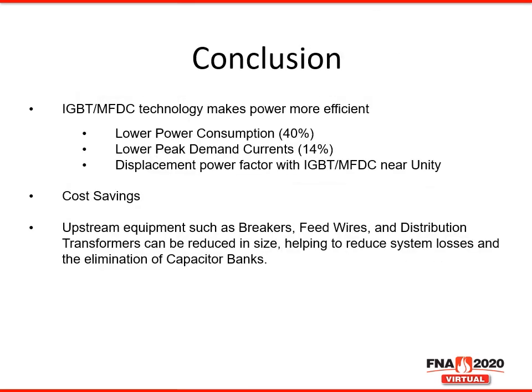In conclusion, and as a summary for this presentation, we have demonstrated a retrofit of a VRT vacuum furnace with an IGBT MFDC power supply. We observed a 40% lower power consumption in kilowatts, a 14% lower peak demand, and a displacement power factor of near unity across the entire cycle. This correlates to real cost savings for furnace applications. Some of the other things that I did not touch on in this presentation are other forms of savings by using an IGBT MFDC system. These are decreased size of breakers, feed wires, and distribution transformers in the facility.